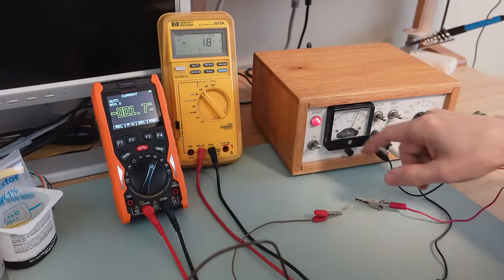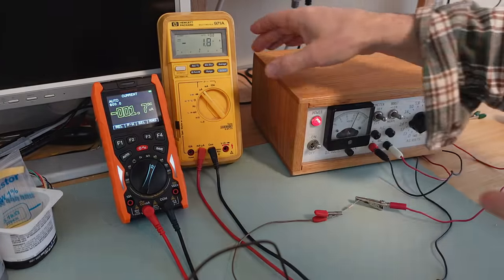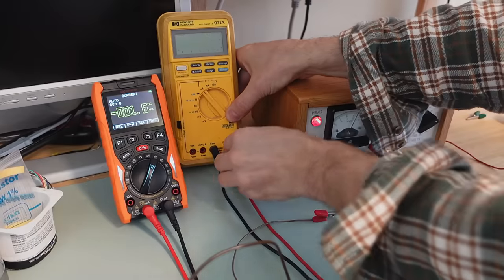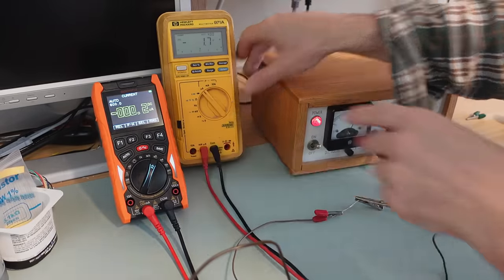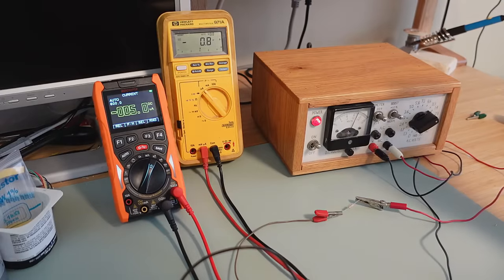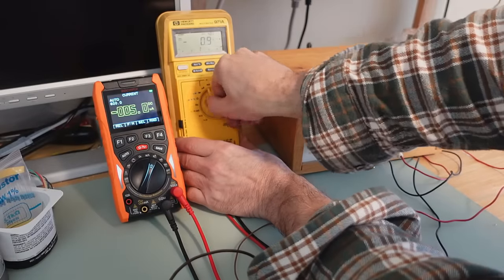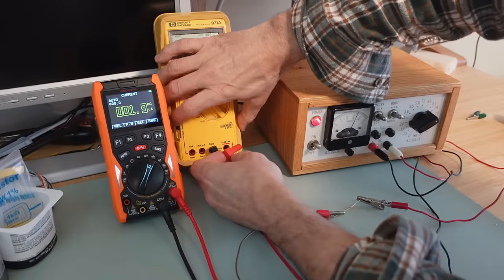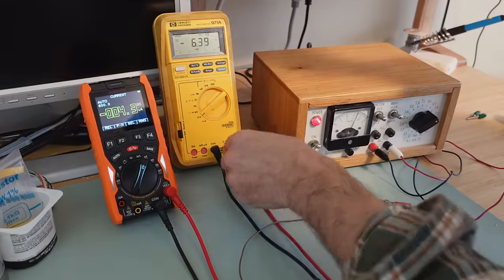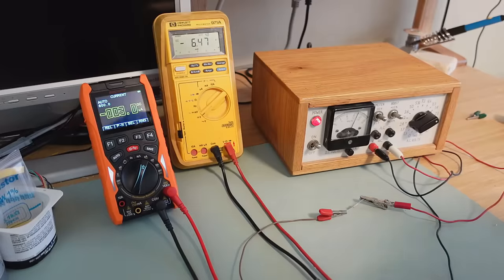I'm using a 10 mega ohms resistor to get a low amount of microamps, and these two meters agree pretty close to each other. Both of these I have to change the connector. So if this is still in ohms on here, it makes an unhappy beep to remind me that I'm doing something wrong. Whereas on this one, if I leave that plugged into here, it just gives me a bogus reading but it doesn't tell me that I'm doing something wrong. And on this one I can't even switch back to volts while I'm in here because to switch back to volts I have to close this shutter and move it over here, and then I can go back to volts. Whereas on here there's no such safety thing. This shutter mechanism is annoying and awkward, but it's saved me a few times.